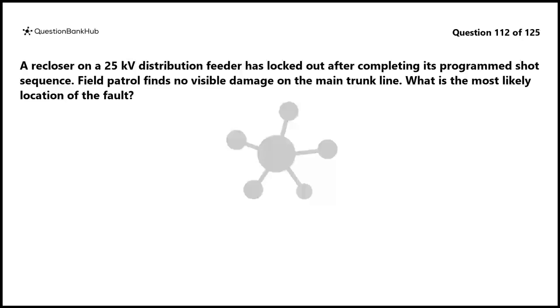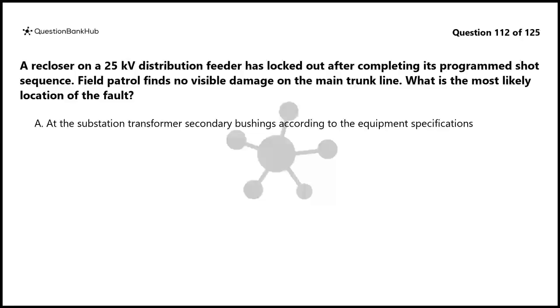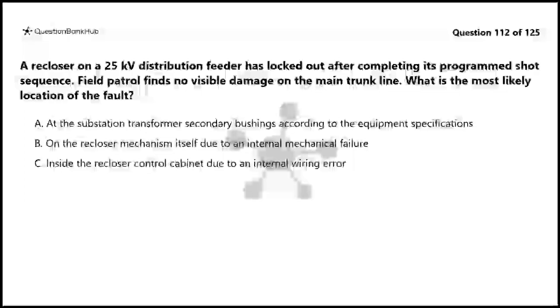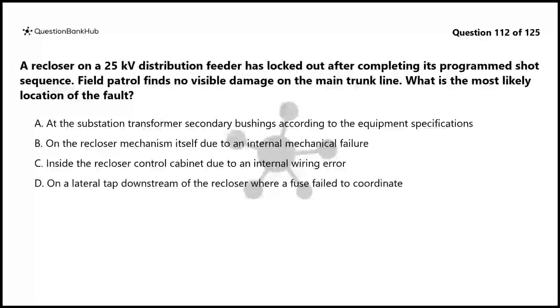Question 112. A recloser on a 25 kV distribution feeder has locked out after completing its programmed shot sequence. Field patrol finds no visible damage on the main trunk line. What is the most likely location of the fault? A. At the substation transformer secondary bushings according to the equipment specifications. B. On the recloser mechanism itself due to an internal mechanical failure. C. Inside the recloser control cabinet due to an internal wiring error. D. On a lateral tap downstream of the recloser where a fuse failed to coordinate.